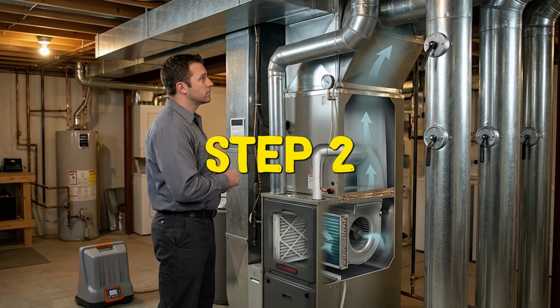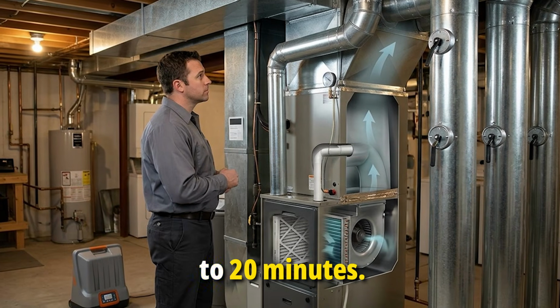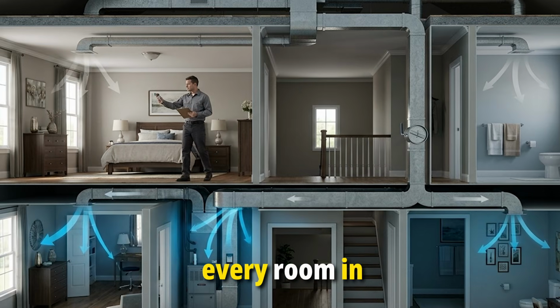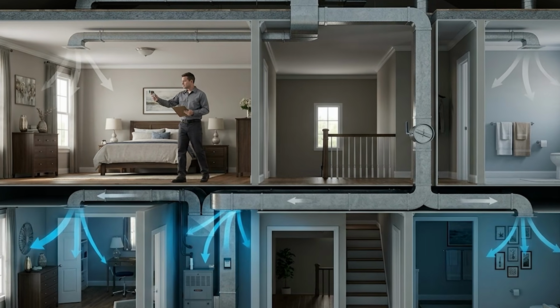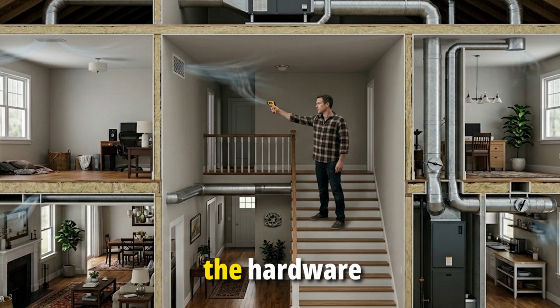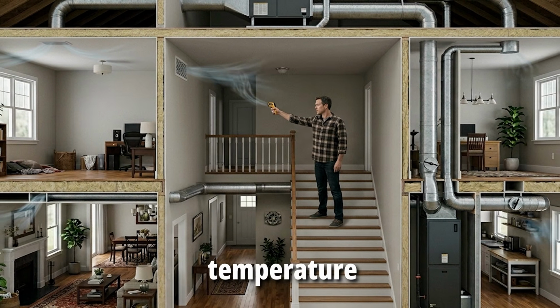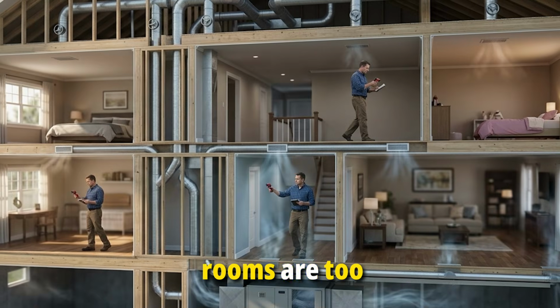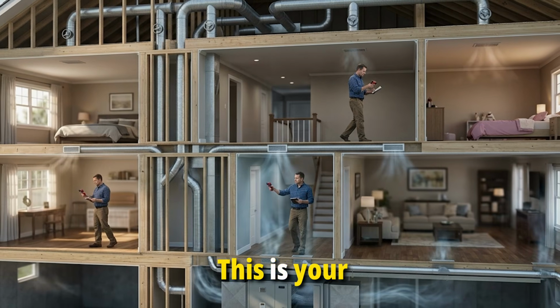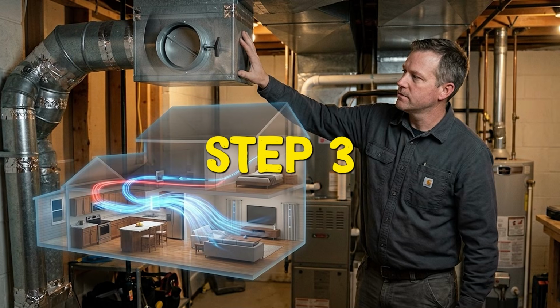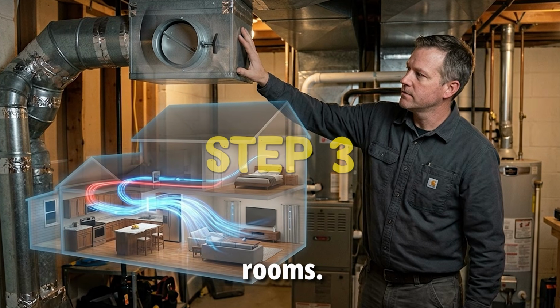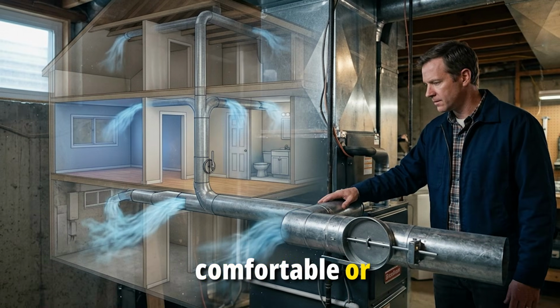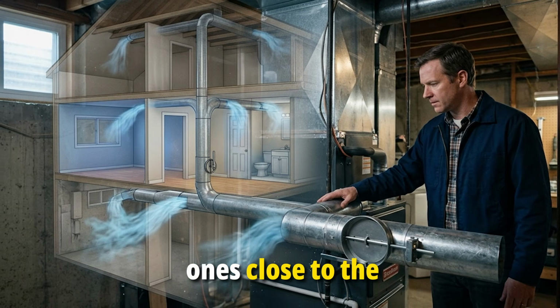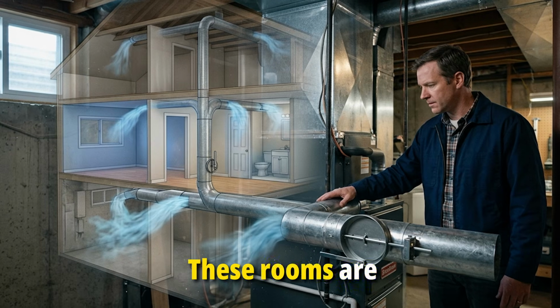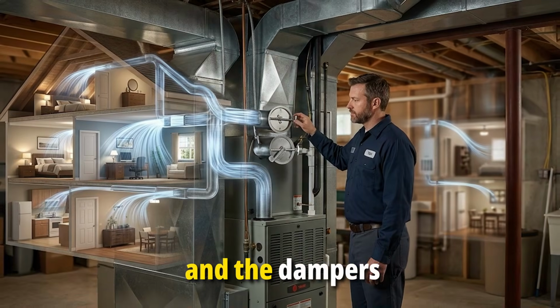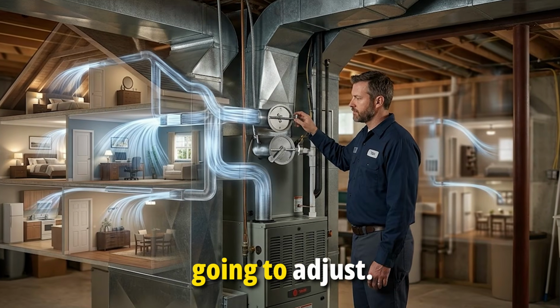Step 2. Turn your system on and let it run for 15 to 20 minutes. Then walk through every room in your house with a simple thermometer. Even a cheap infrared one from the hardware store works perfectly, and measure the temperature in each space. Note which rooms are too cool and which are too warm. This is your baseline. Step 3. Find the dampers feeding your overserved rooms. The rooms that are already comfortable, or even a little too cold. The ones close to the air handler. These rooms are receiving more than their share, and the dampers feeding them are the ones you are going to adjust.